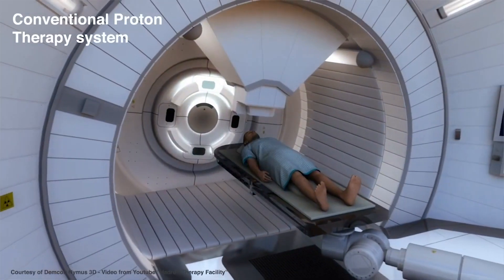Why is this? In proton therapy, the level of energy tells you exactly where protons stop. So if you need to treat a superficial tumor, you need a low energy. With the machines available today, the designs are circular, so protons get accelerated in a circular manner and come out at the same full energy. That means if you have to treat a superficial tumor, you have to put absorbers at the end of the accelerator, which absorb the energy — but that process is highly inefficient, creating significant unwanted radiation.